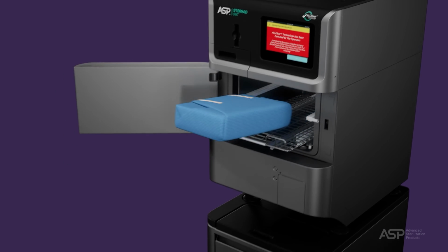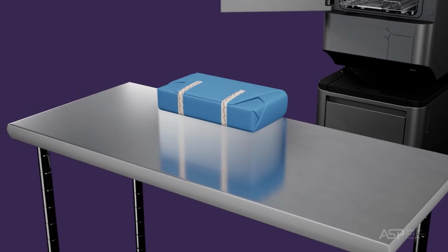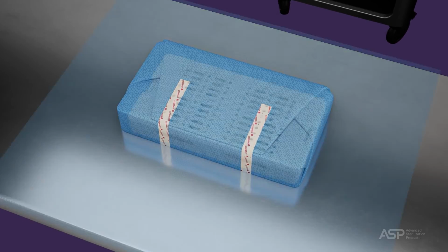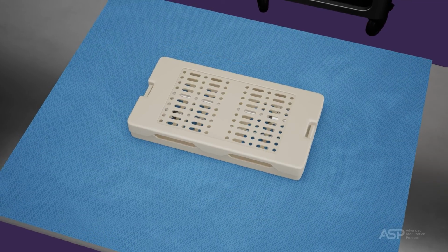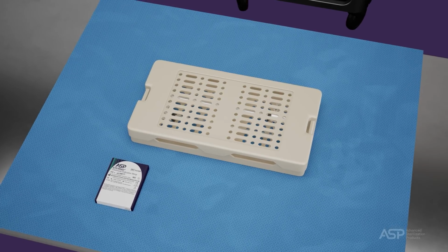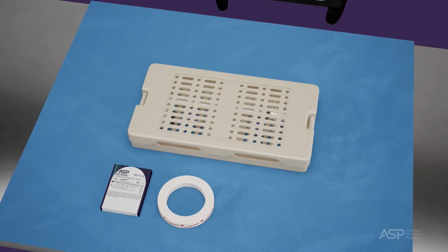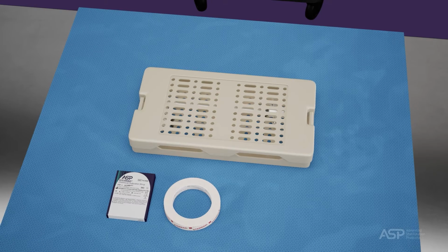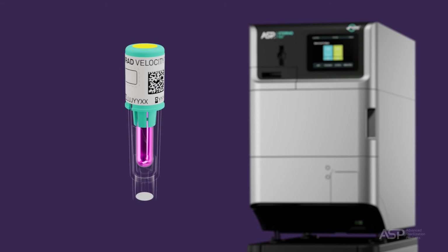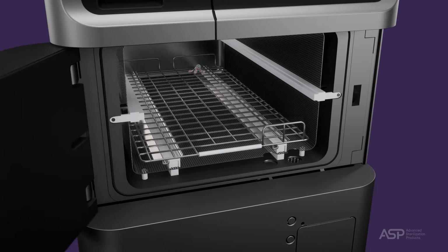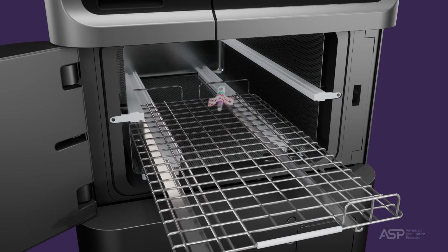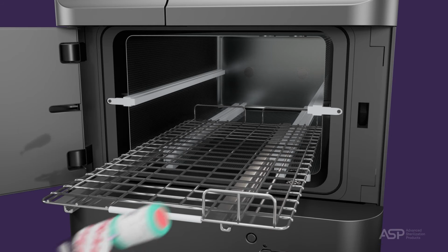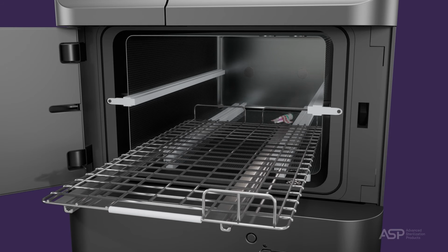When removing items from the sterilizer following a canceled cycle, loads from canceled cycles should be rewrapped using new package materials, STERRAD Chemical Indicator (CI) strips, and SealSure Chemical Indicator (CI) tape. If a biological indicator (BI) was used in the canceled load, the previously used BI must be disposed of per your hospital or healthcare facility's policy, and a new BI must be placed in the chamber before restarting.